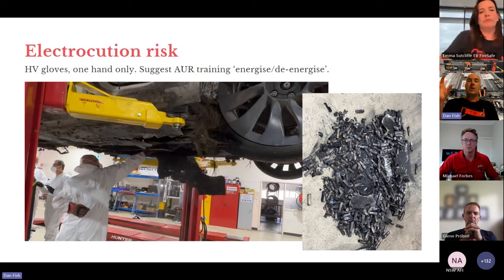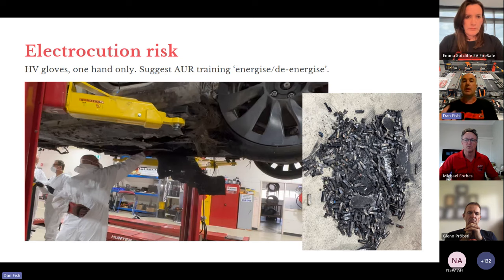So if you were to be doing this sort of work, this is what's called the one hand rule. There's also ways you can do probing with a contact detector - they might call it chopsticks - holding both the positive and the negative contact of your voltmeter or multimeter in one hand to do that probing as well. The only way to check for a voltage in that situation would be with a contact type detector rather than non-contact. You may be able to use a clamp type meter.